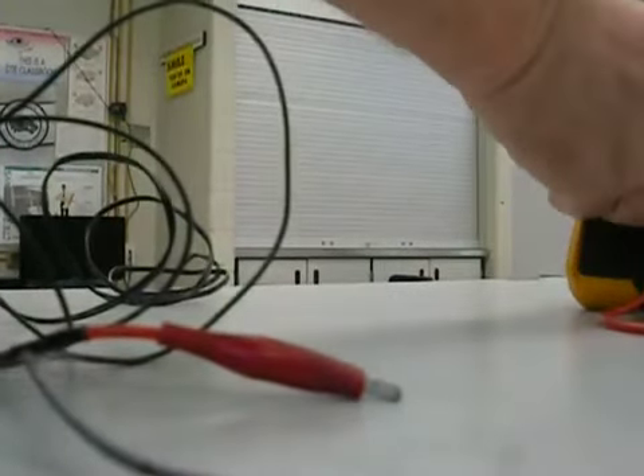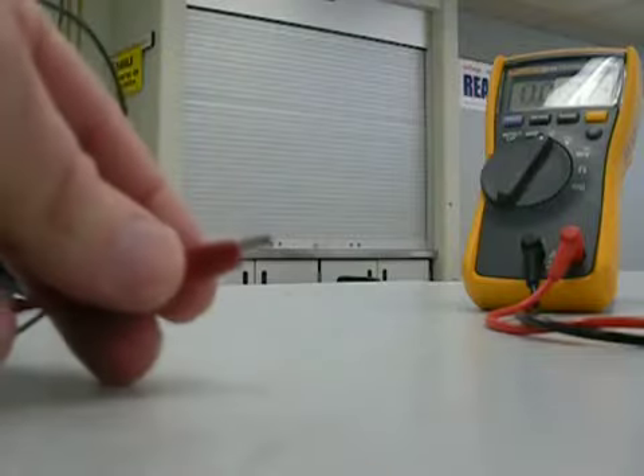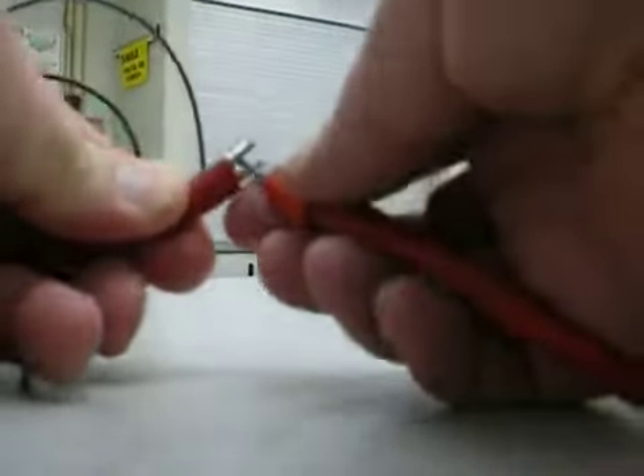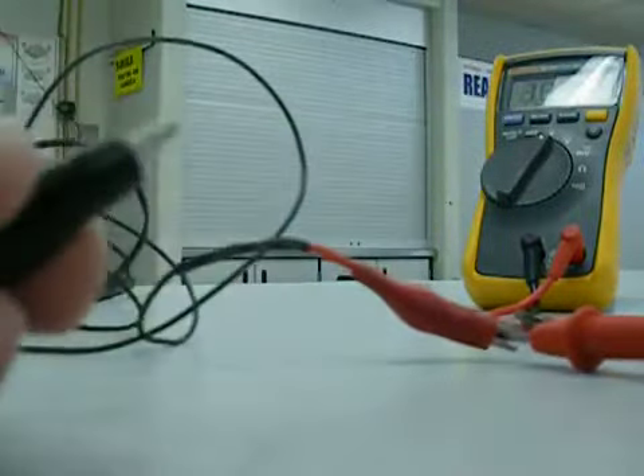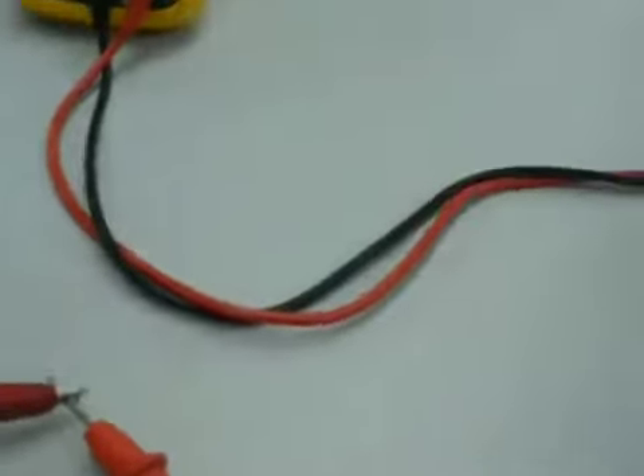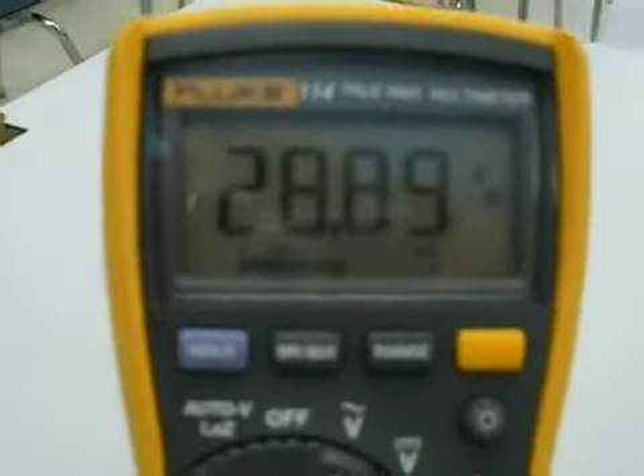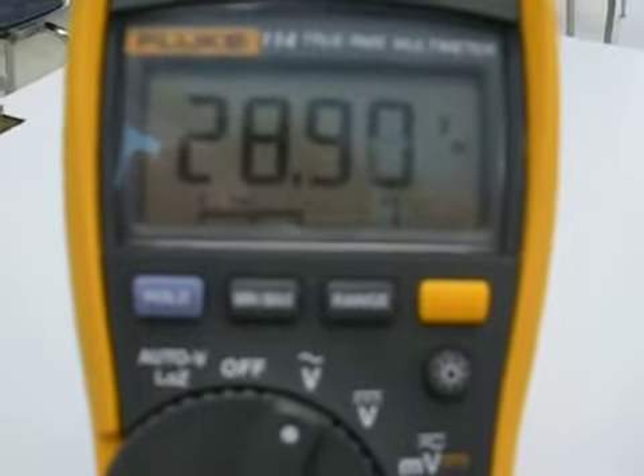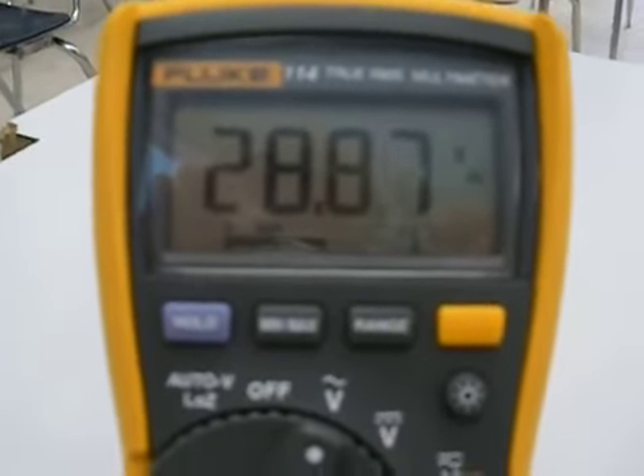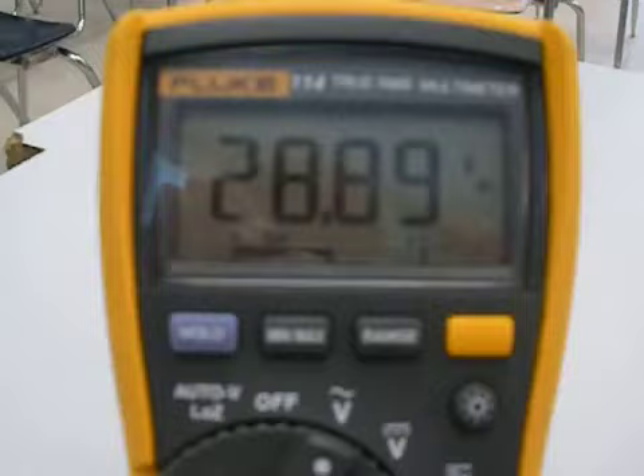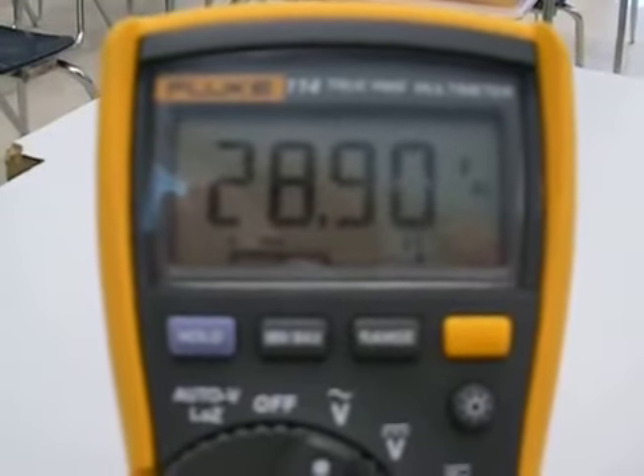Then I want to switch this meter to AC voltage. And because this is AC, even though I'm connecting red to red, black to black, I don't have to. AC does not have polarity. Okay, so I got that hooked up. And look at this. I have 28.8 volts coming out of that transformer, which since the label said 24 volt AC transformer, that's about right.